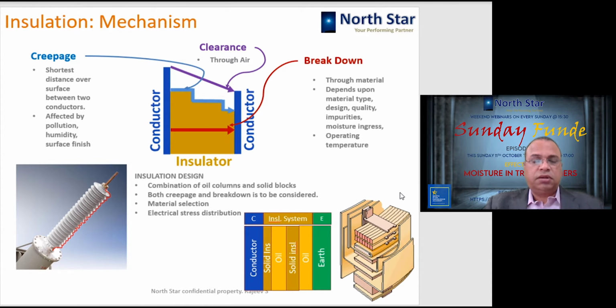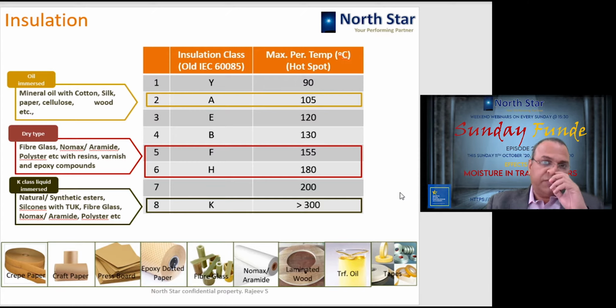Okay, so this is about the insulation mechanism. As far as the types of insulation are concerned, these are different classes, you know it well. Earlier, in older days, they were alphabetically designated categories. Now the IEC has revised this, and they have switched over to values of temperature, the maximum hotspot temperature which that particular insulation system can sustain. So for example, class A can work up to 105 degrees centigrade. Our normal mineral oil filled transformers are designed with class A insulation, which is mostly cellulose based items immersed in the mineral oil. So this transformer can work up to 105 hotspot temperature.